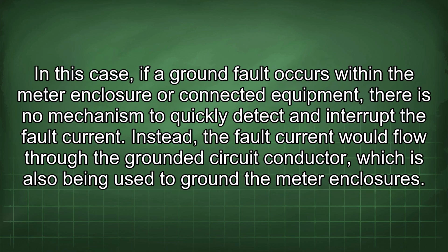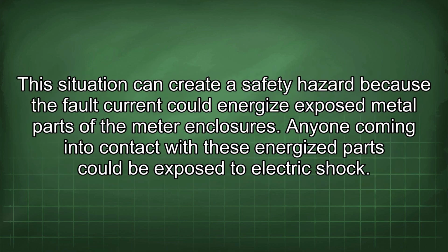In this case, if a ground fault occurs within the meter enclosure or connected equipment, there is no mechanism to quickly detect and interrupt the fault current. Instead, the fault current would flow through the grounded circuit conductor, which is also being used to ground the meter enclosures. This situation can create a safety hazard because the fault current could energize the exposed metal parts of the meter enclosures. Anyone coming into contact with these energized parts could be exposed to electric shock.